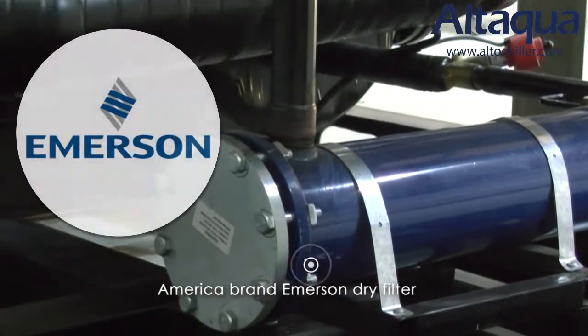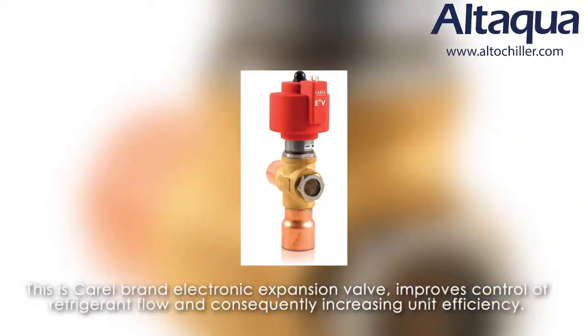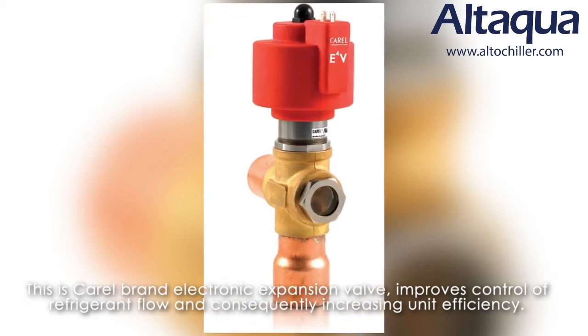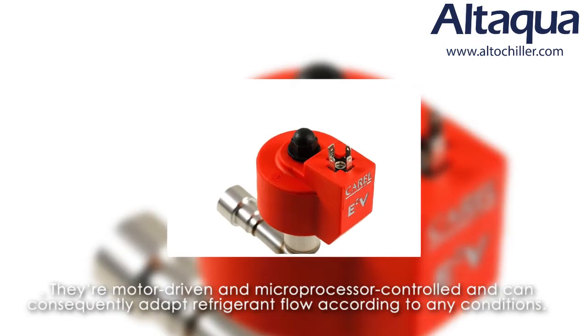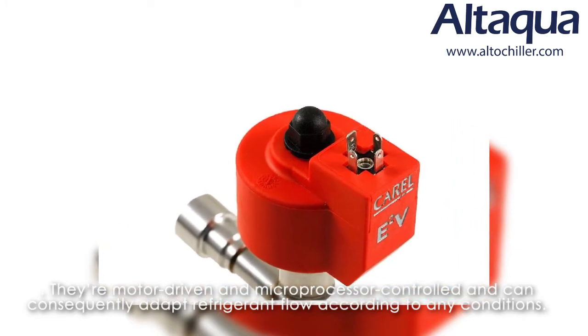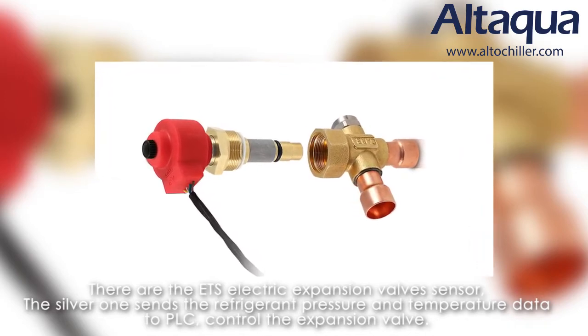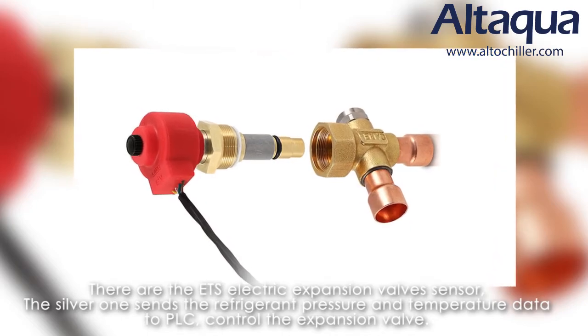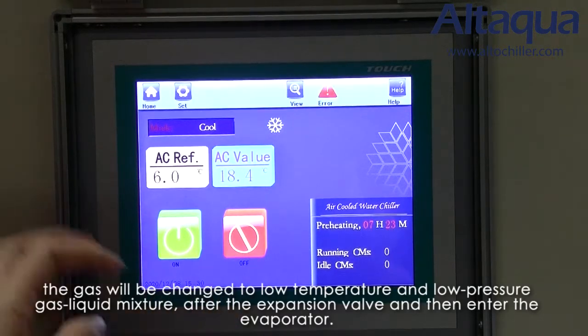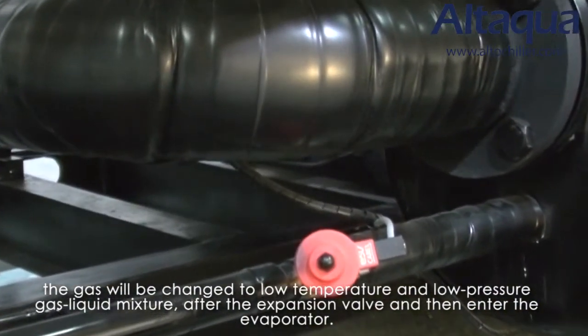There is an Emerson brand dry filter, which can absorb moisture and small particles from the refrigerant. This is a Carel brand electronic expansion valve, which provides improved control of refrigerant flow and consequently increases unit efficiency. They are motor-driven and microprocessor controlled, and can adapt refrigerant flow according to any conditions. There is also the ETS electronic expansion valve sensor — the silver one sends refrigerant pressure and temperature data to the PLC to control the expansion valve. The gas will then be converted to a low-temperature, low-pressure gas-liquid mixture after the expansion valve and enter the evaporator.